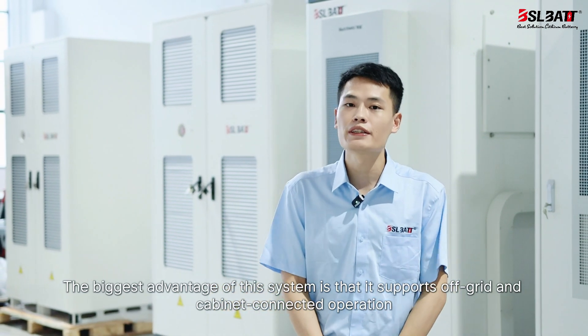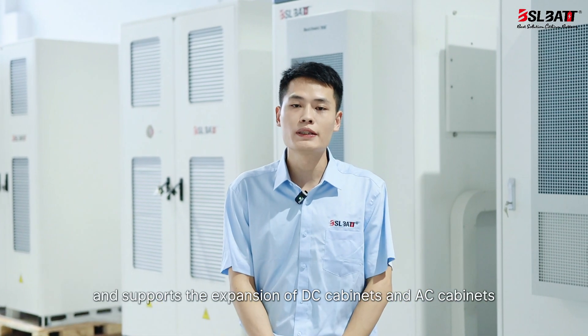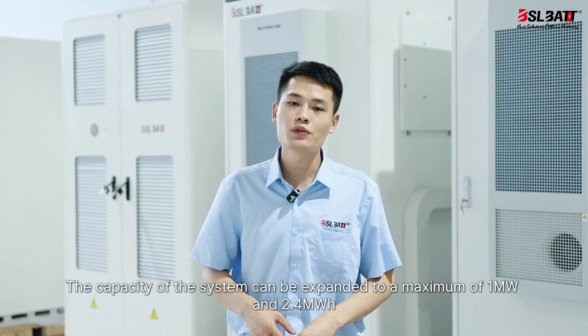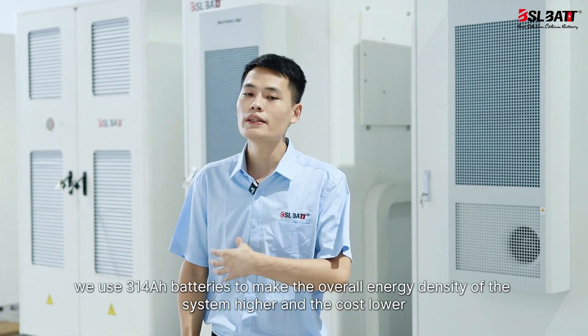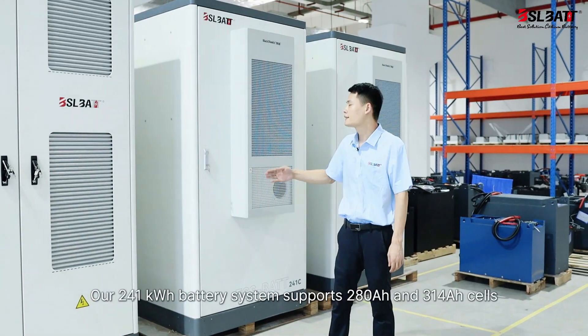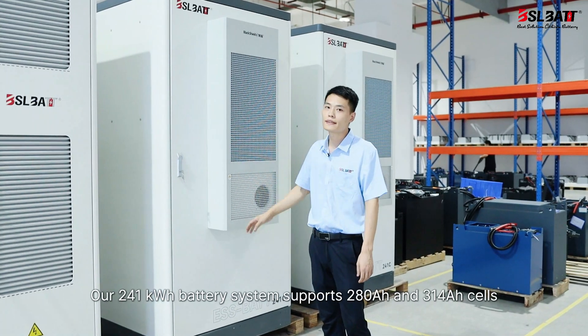The biggest advantage of this system is that it supports off-grid and cabinet-connected operation, and supports the expansion of DC cabinets and AC cabinets. The capacity of the system can be expanded to a maximum of 1 MW and 2.4 MWh. We use 314Ah batteries to make the overall energy density of the system higher and the cost lower. Our 241 kWh battery system supports 280Ah and 314Ah cells.